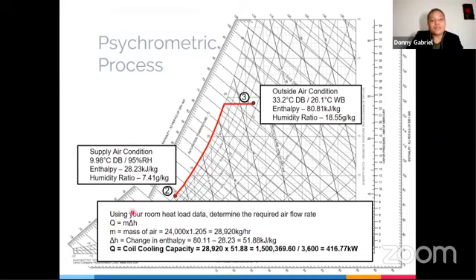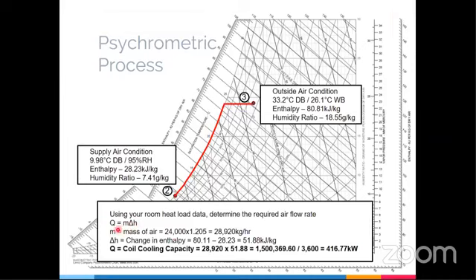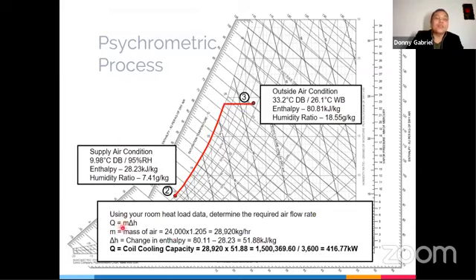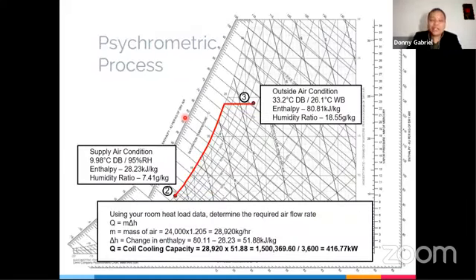Same formula, Q is equal to M delta H. So now we don't know the Q, but we know we need 24,000 cubic meter of air. So using the difference in enthalpy, the enthalpy of the outdoor air is 80.81. The enthalpy of the supply air condition is 28.23. You get their difference. Change of enthalpy is 51.88 multiplied by your mass of air at 24,000 cubic meter per hour, changed to kilogram. You will get about 416 kilowatt. So which means this coil is about 400 kilowatt. The size of this coil is about 400 kilowatt. We got it by calculating first what is the amount of air needed here, and using the amount of air needed here, we were able to determine the size of the coil using our psychrometric analysis, using our psychrometric chart.